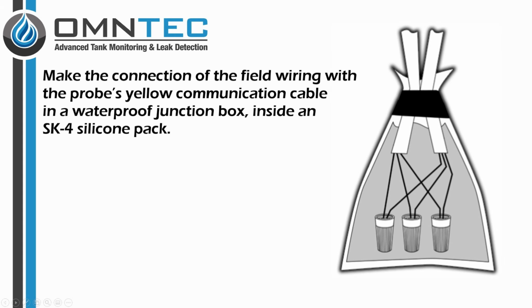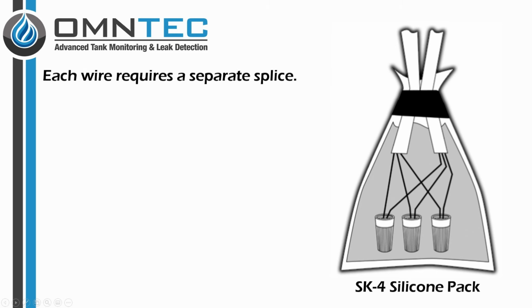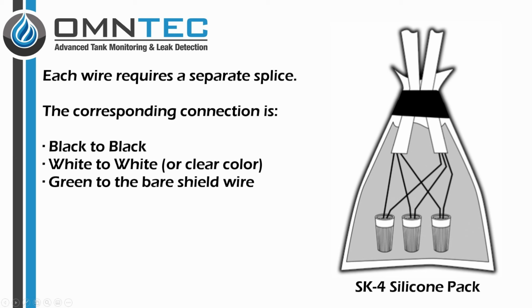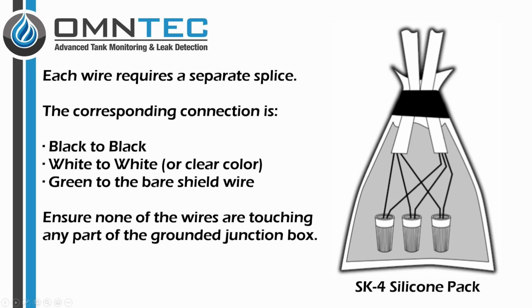Make the connection of the field wiring with the probe's yellow communication cable in a waterproof junction box inside an SK4 silicone pack. Each wire requires a separate splice. The corresponding connection is black to black, white to white or clear color, and green to the bare shield wire. Ensure none of the wires are touching any part of the grounded junction box.